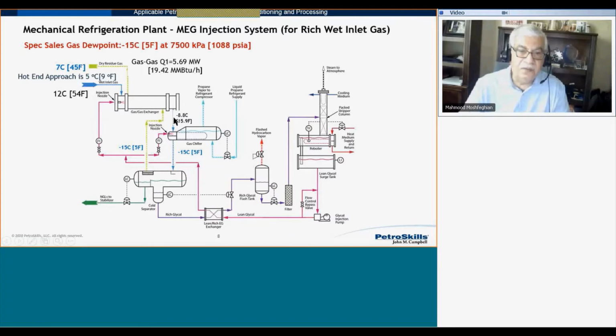So the sales gas is the cooling media and it's on the shell side, but the process gas is inside, so I come out here, three-phase. I got gas phase, liquid hydrocarbon, and aqueous phase, which is glycol and water. So this is a pre-cooling upstream of the chiller. And you'll see that this gas exchanger is going to remove a good portion of total heat removal from the process gas.